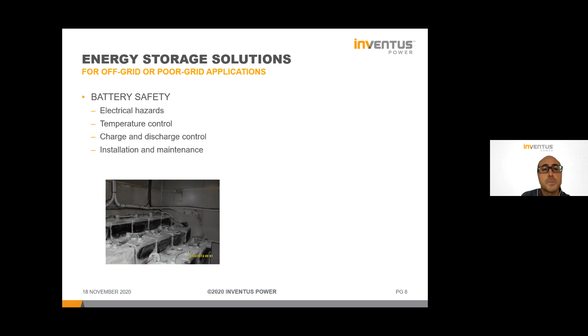Charge and discharge control, installation and maintenance. I've created a quick checklist of what to think about when designing a battery system for an off-grid system. Take into account the breakers, both AC and DC. You'll have breakers on the DC side, from the PV to the charge controller, from the charge controller to the batteries, and from the batteries to the inverter, all rated accordingly.